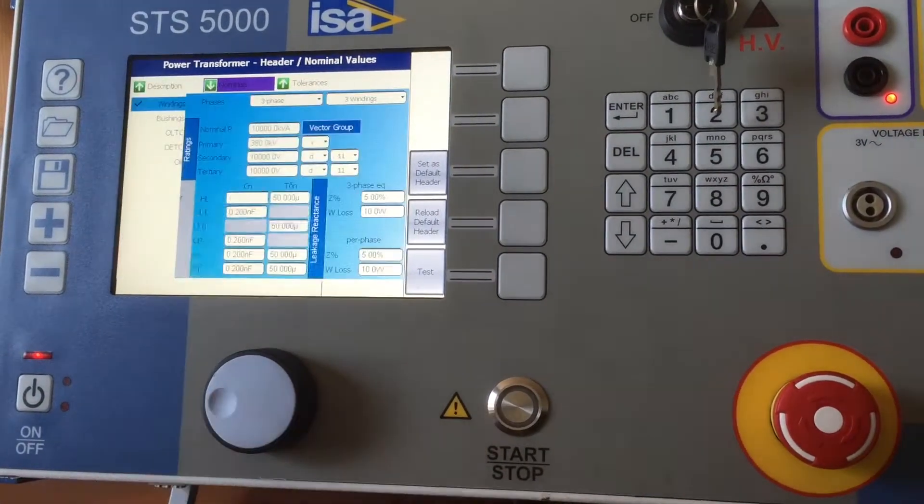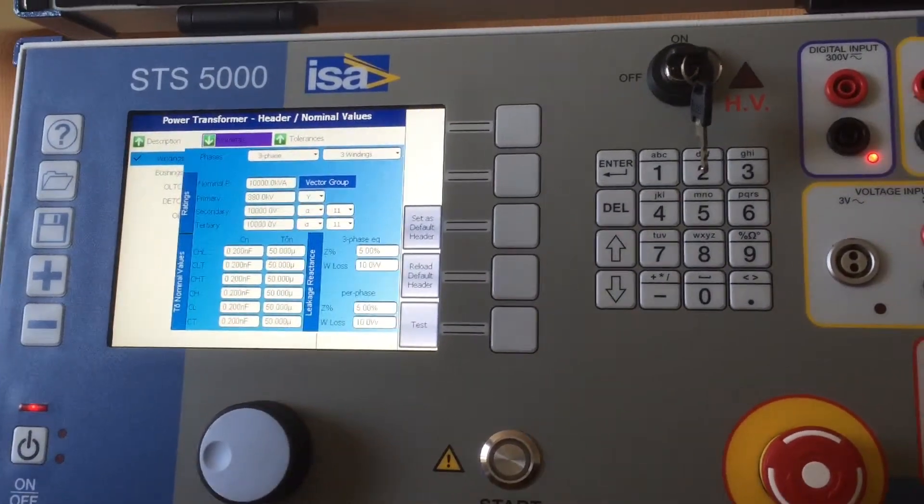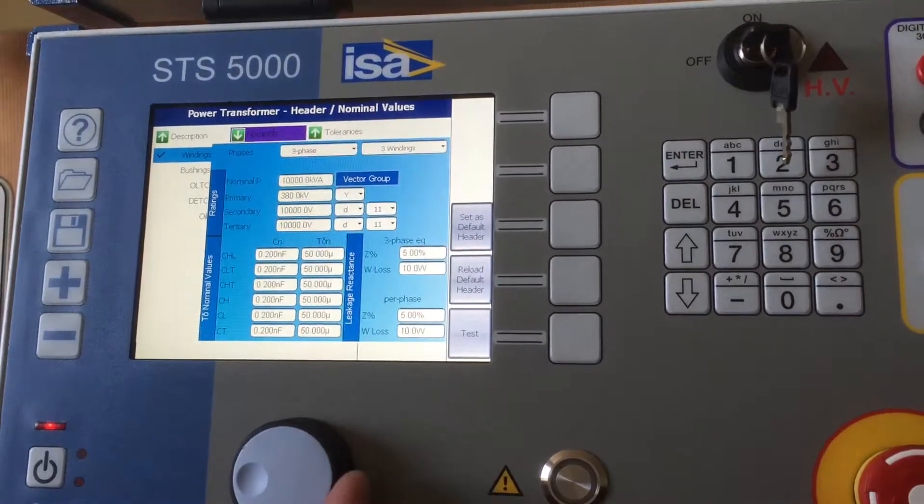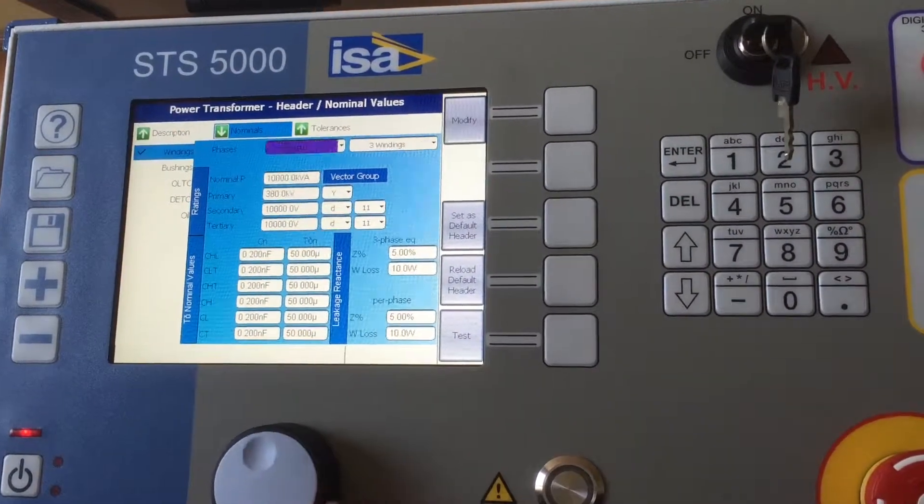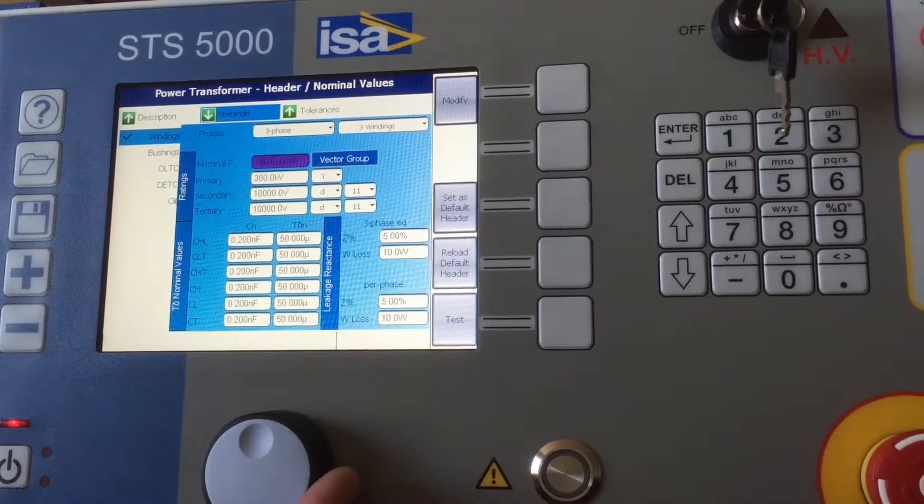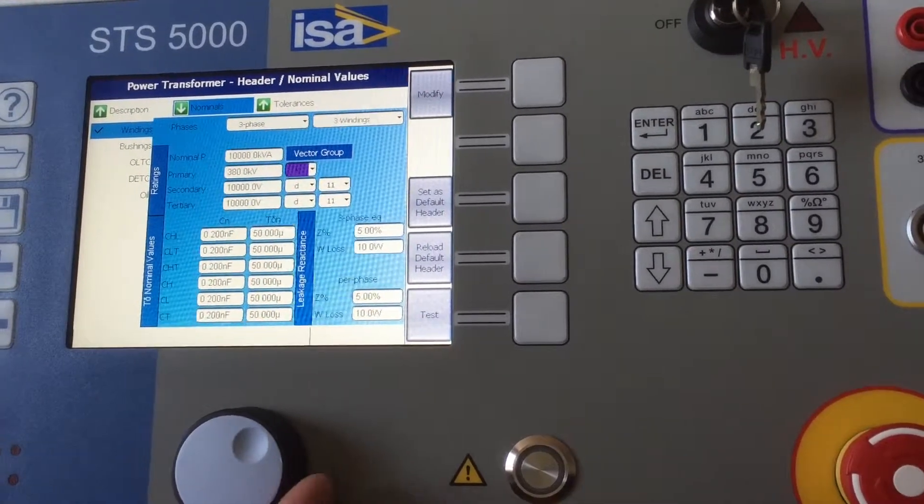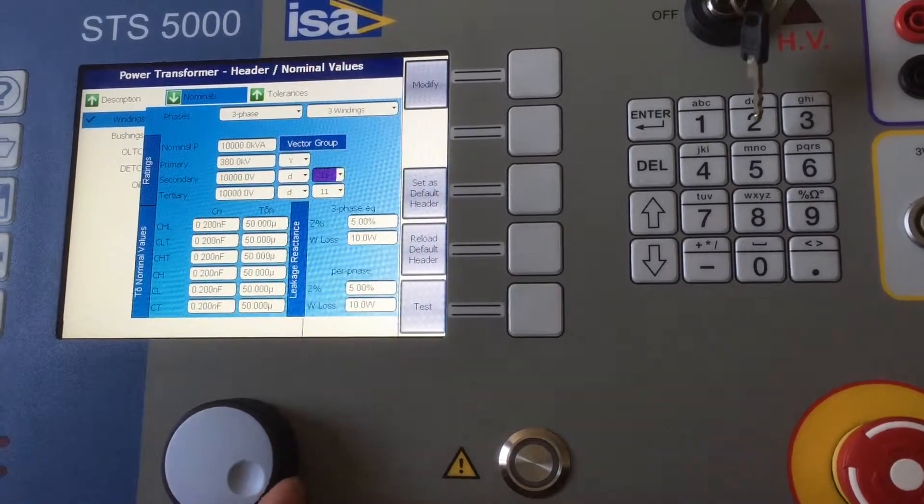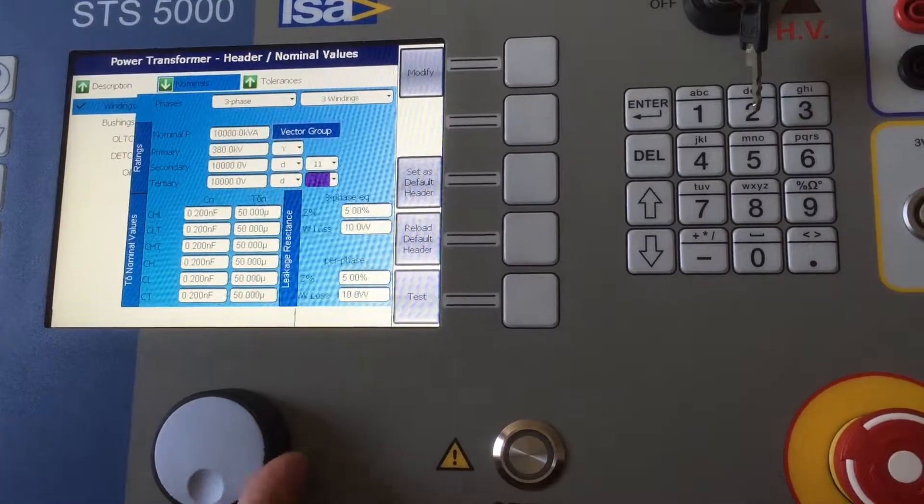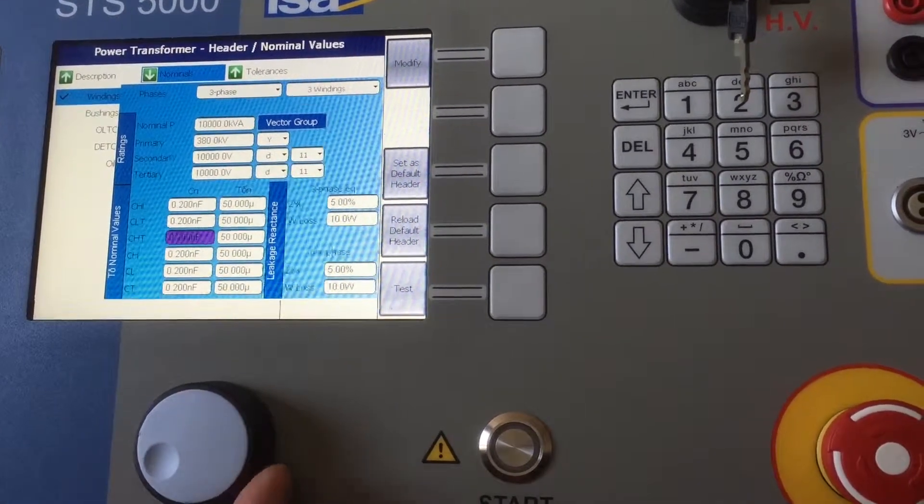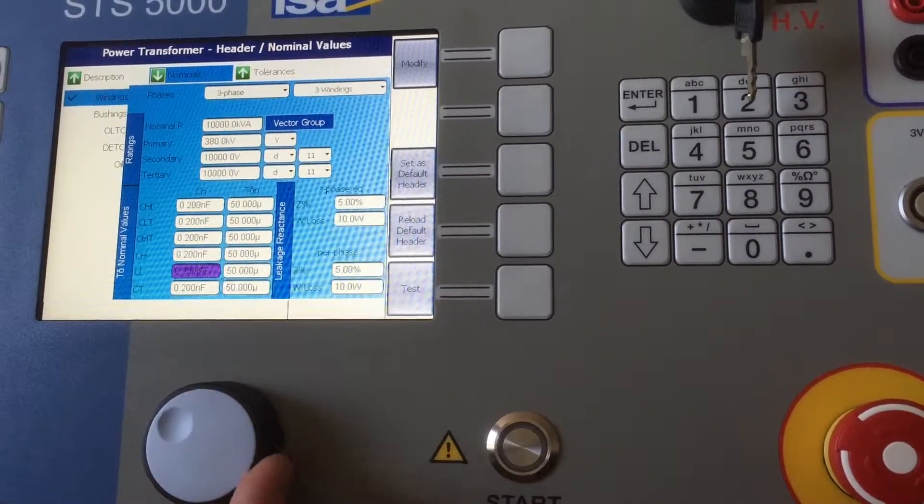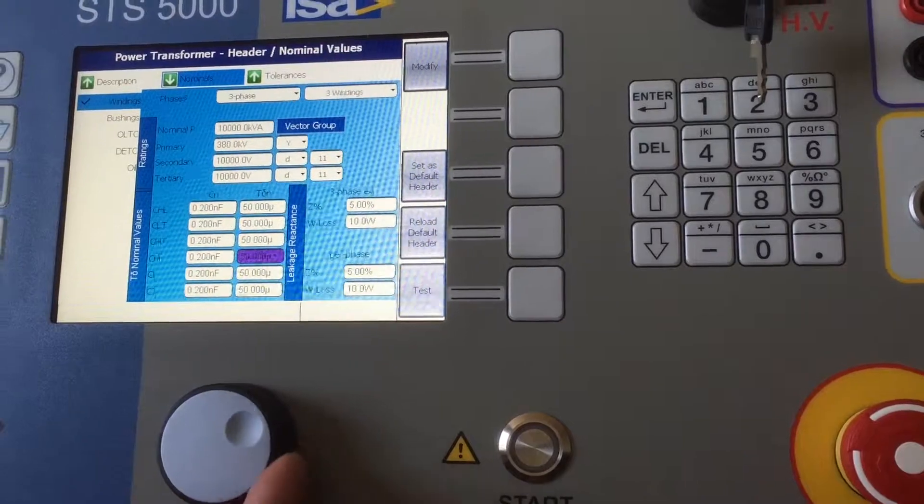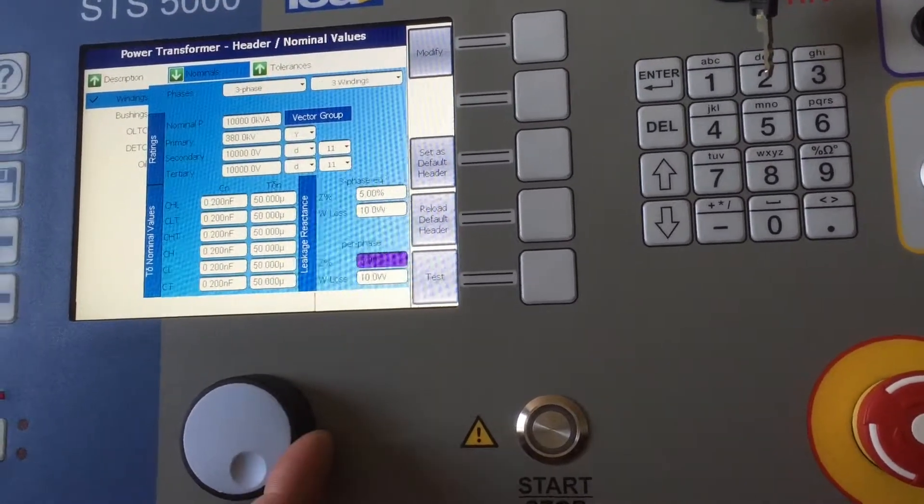Here the nominals are a little bit more difficult because power transformer is more complex than a current or voltage transformer. One would have to punch in the nominal power, primary, secondary and if it exists a tertiary, of course also the vectorial group and the nominal values for tan delta which is basically capacitance or power factor.